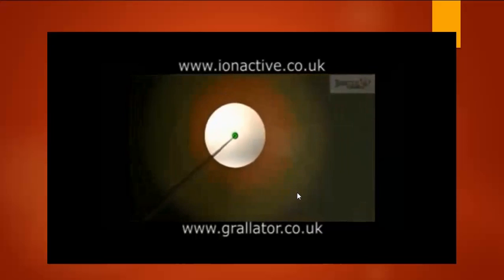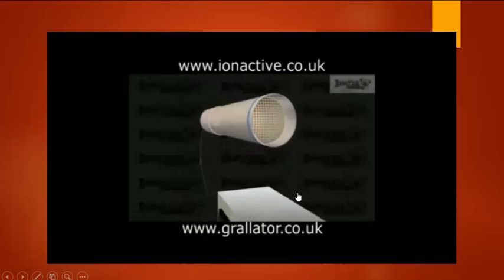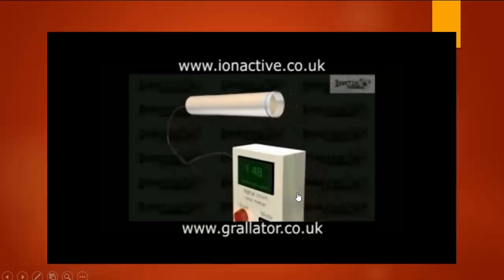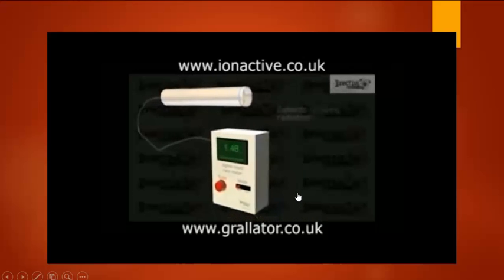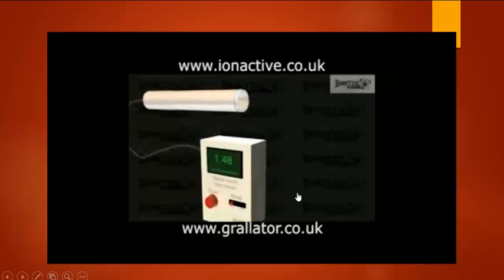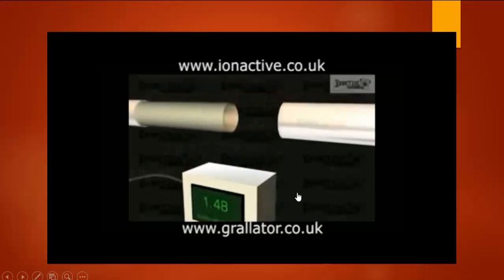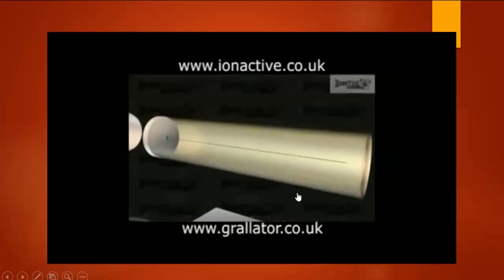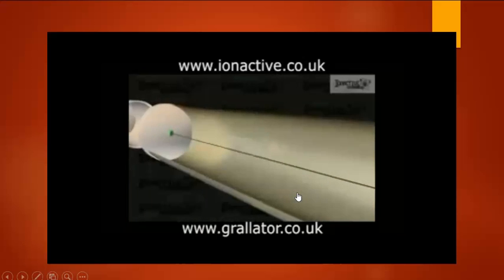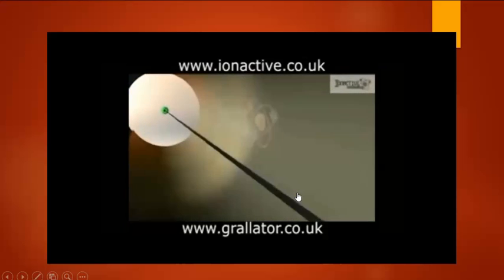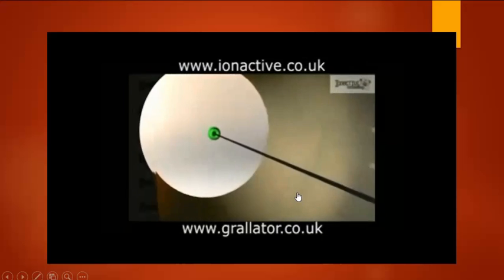Geiger or GM counters are one of a class of gas-filled radiation detectors that operate by using the ionizing nature of alpha, beta and gamma radiation. The GM tube is a sealed metal cylinder containing a low-pressure inert gas such as argon or neon. A thin metal wire runs down the centre of the tube, which is electrically insulated from the outer cylinder at the rear of the tube.